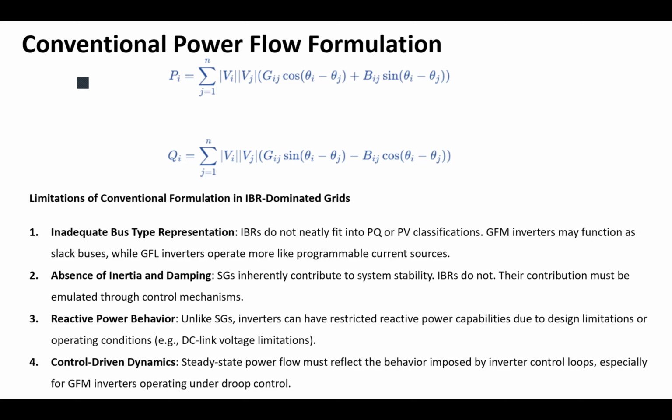Because it's constantly changing, because it's reading the grid, following, so you can't describe it. Half. Yeah. Okay, it's constantly changing is not quite true, because a rotary machine is also constantly changing, because it has to address the variation in demand. Not as fast as inverters, but they are changing also. But the second half of your statement was true, because they have to read the voltage variables from the terminals in order to calculate the P and Q.